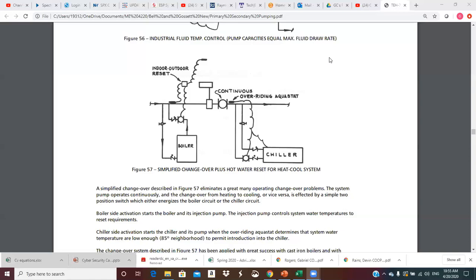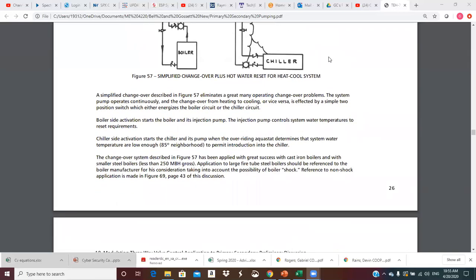The changeover system described in this figure has been applied with great success with cast iron boilers and with small steel boilers less than about 250,000 MBH gross input. Application to large fire tube steel boilers should be referenced to the boiler manufacturer for their consideration, taking into account the possibility of boiler shock. We might run into this a little bit more later.